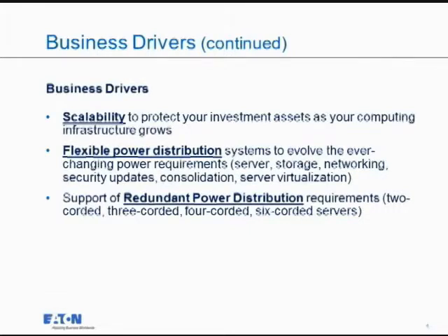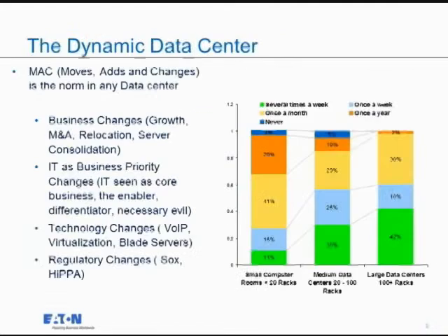So here's some data to substantiate and corroborate the example I gave a couple minutes ago, and that's a dynamic data center. We went out and we surveyed, I think it was about 350 customers of ours or applications, and we asked, how often are you making what's referred to as MACs, modifications, additions, and changes in your data center floor? And what you'll see, if you look at that right-hand column right here, is 42% are doing it several times a week. And this is, again, a slightly dated example.